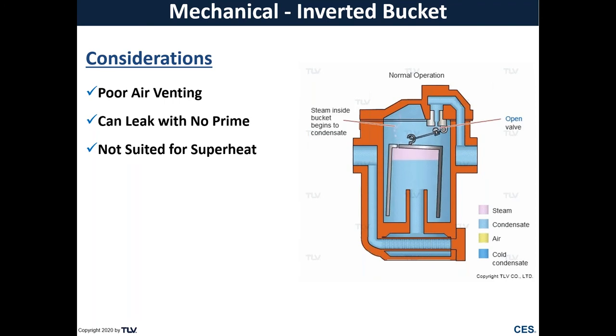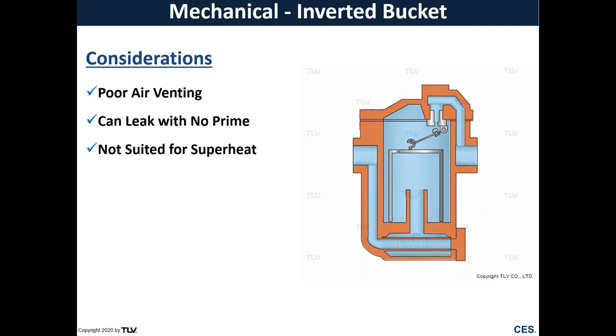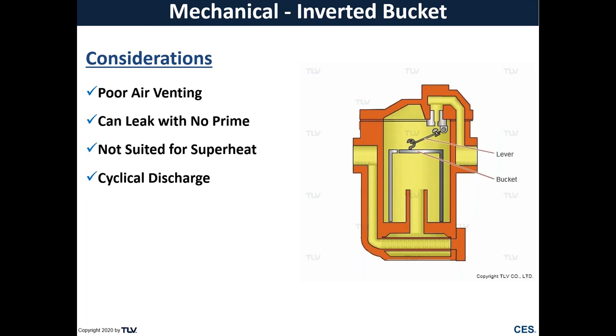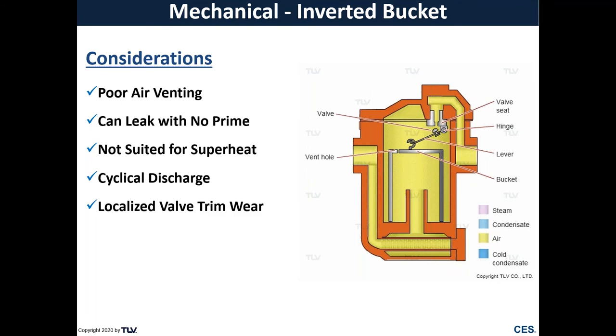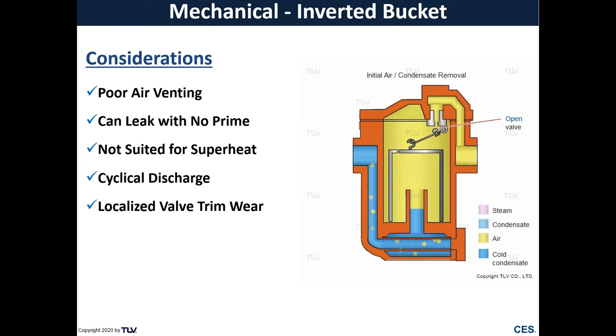One of those situations that you may lose your water prime is during superheat. So this trap is not suitable for superheat, as that superheat could vaporize your water prime inside of the steam trap. It is a cyclical discharge, so that's just something you have to consider when using this trap. And due to the linkages, single valve head and single valve seat, it's kind of susceptible to localized wear, which will eventually lead to leakages as well as trap failure.